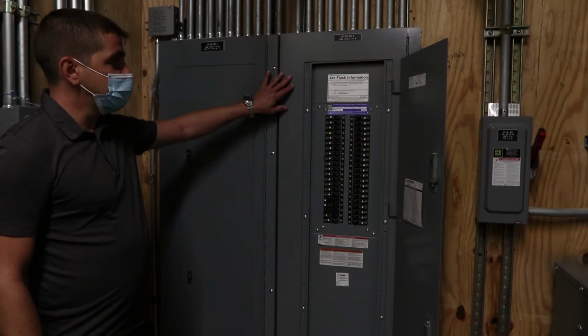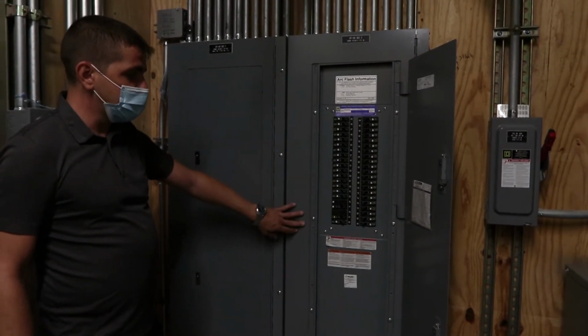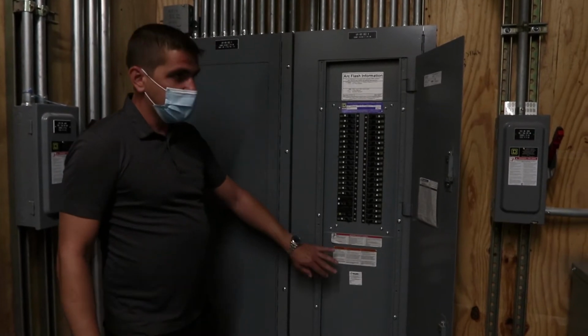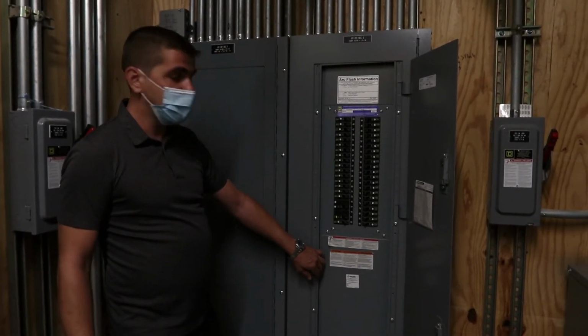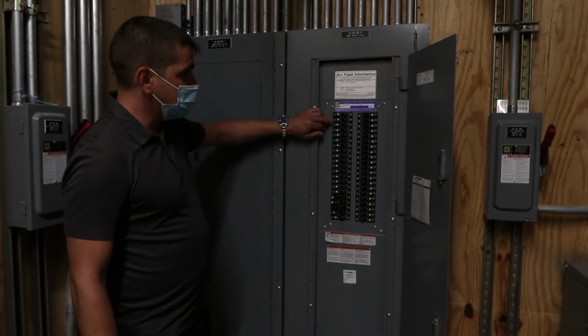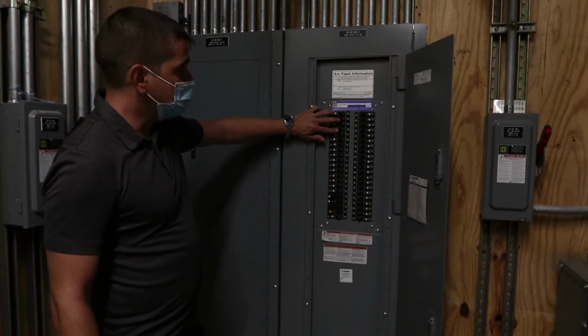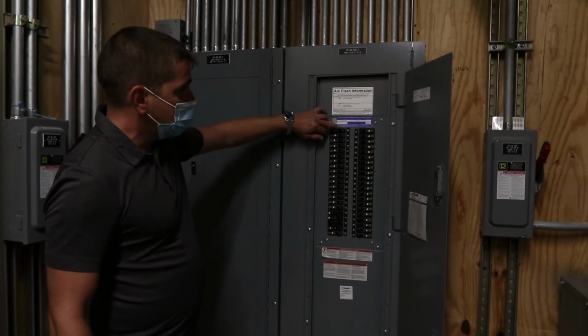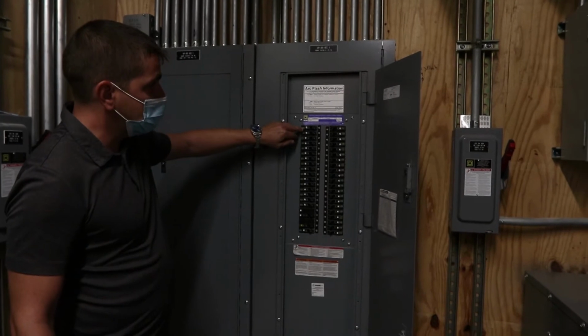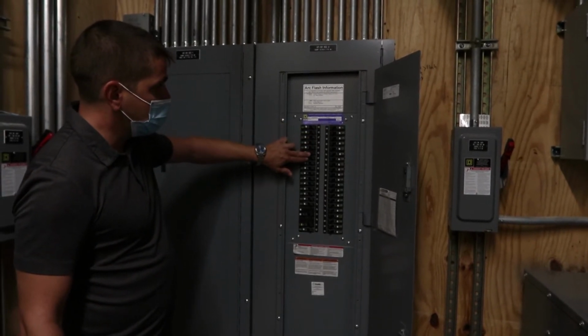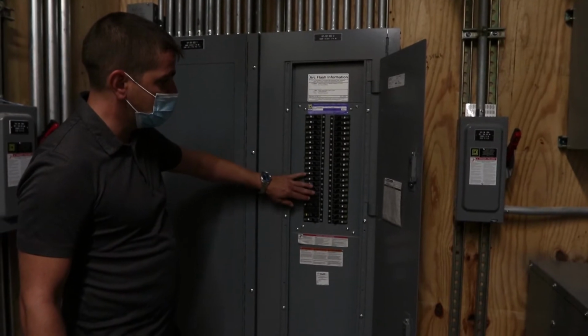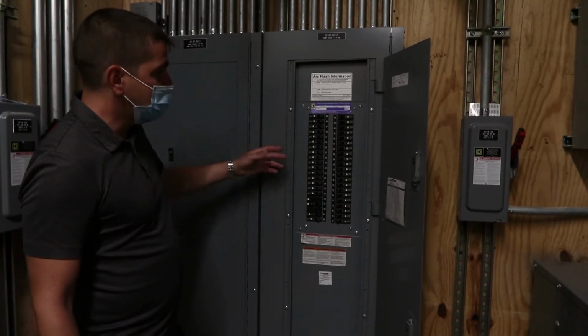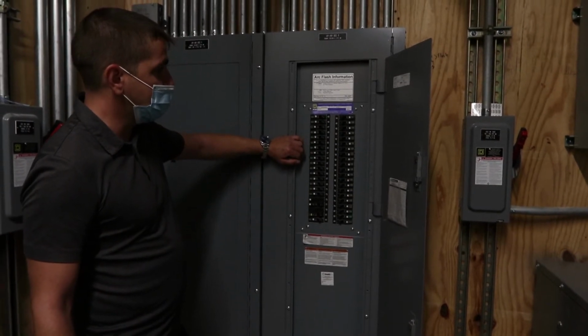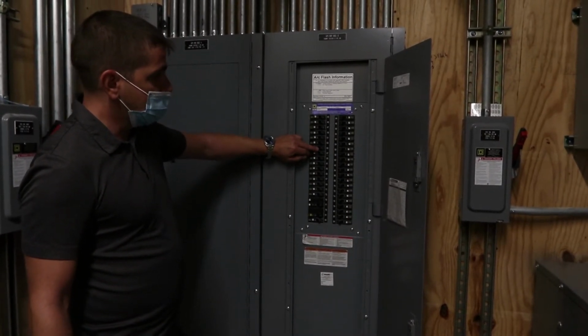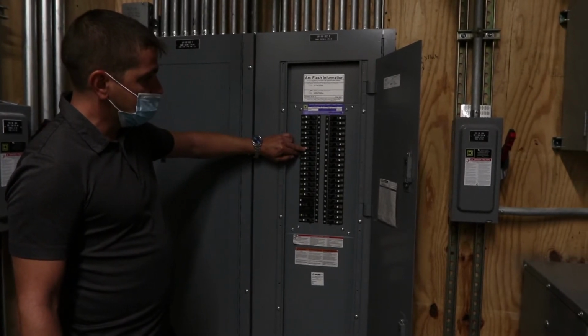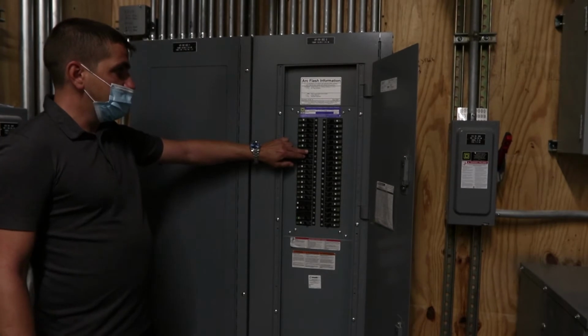The next portion we're going to cover is a typical panel board. This one isn't equipped with a main breaker, only with main lugs. It's fed from the distribution panel that we covered before. It has all of the circuit breakers which fit in the equipment, for all of the outlets, receptacles, and lighting. Circuit breakers, once again, don't have to be serviced or maintained, just make sure from time to time that breakers are in the on position and that the equipment is not de-energized. In the rather unlikely event that a breaker trips, it's going to be in the middle position. It has to be brought to the off position fully before it can be reset and the equipment energized.